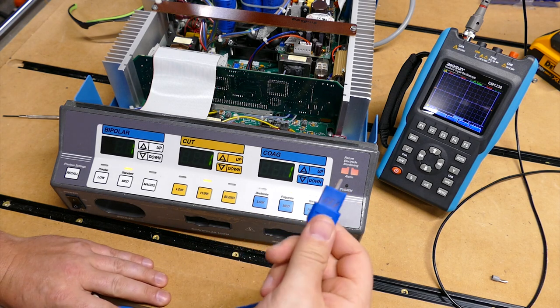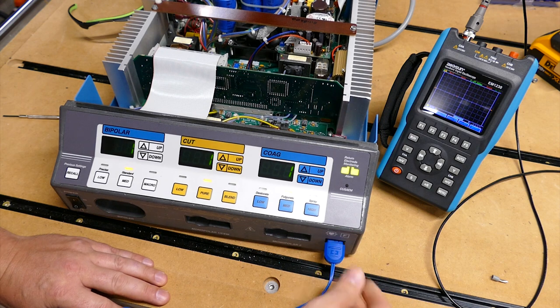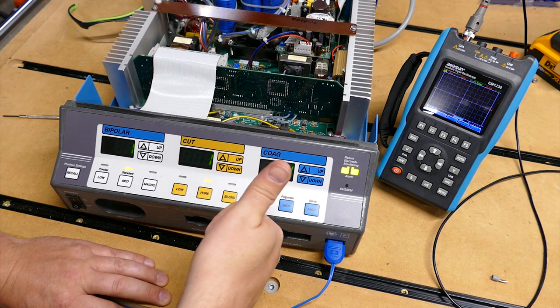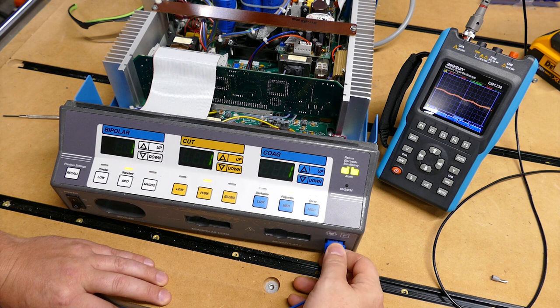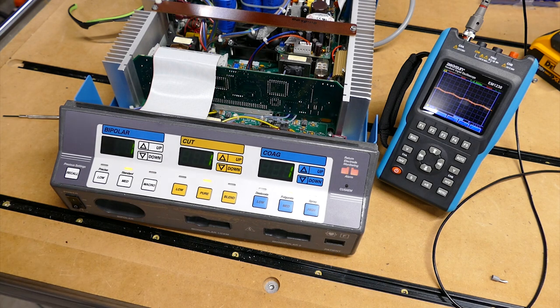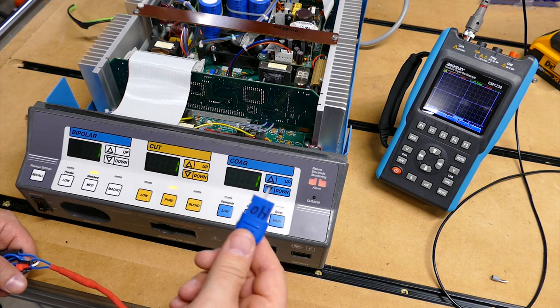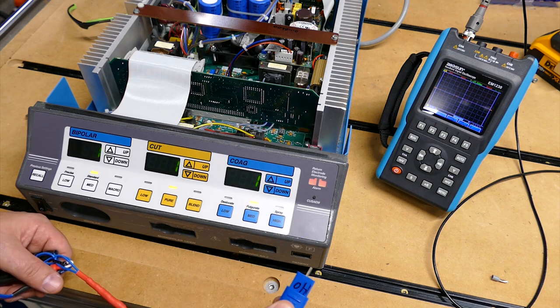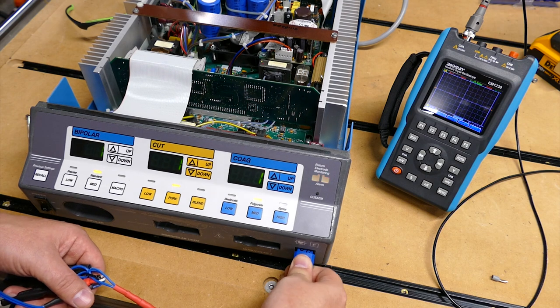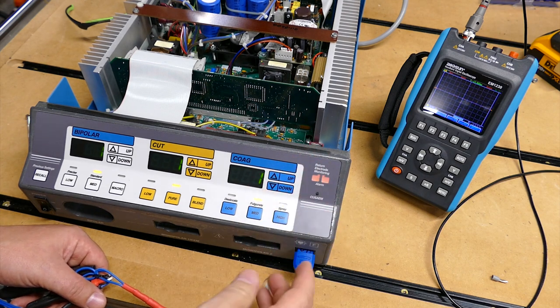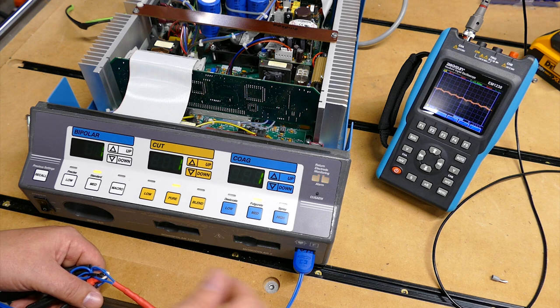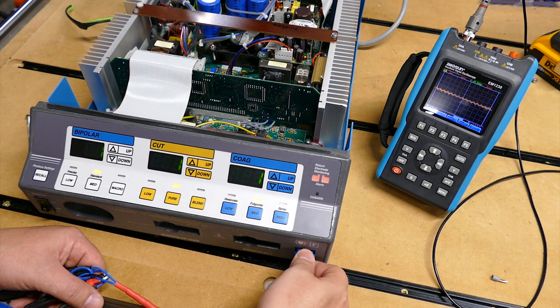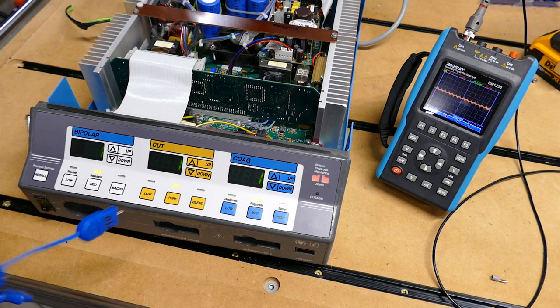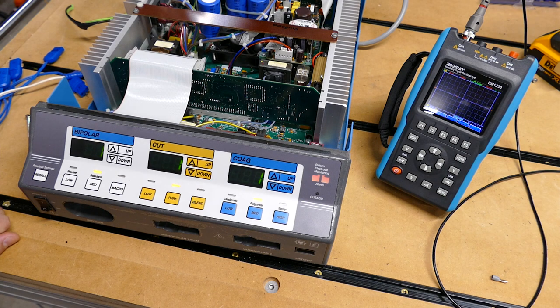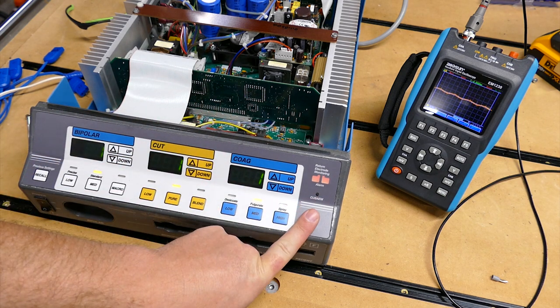Next, I tried the 135 ohm key. And it's good to go. Then we tried the 140 ohm key, and it should not pass. You can see immediately it recognizes it's over its preset limit, which is 135 ohms, goes immediately to red, and that would be a successful calibration. So that's calibrating the REM circuit on one of these old workhorses.